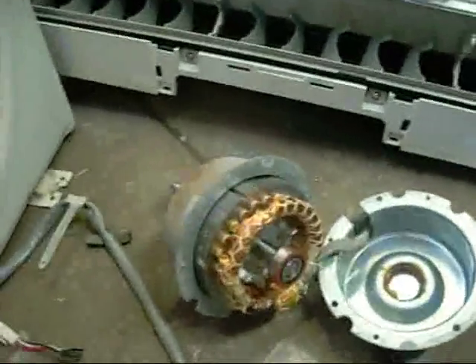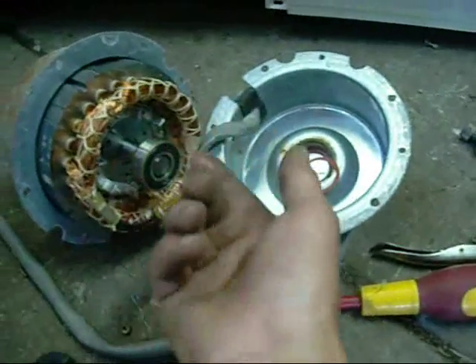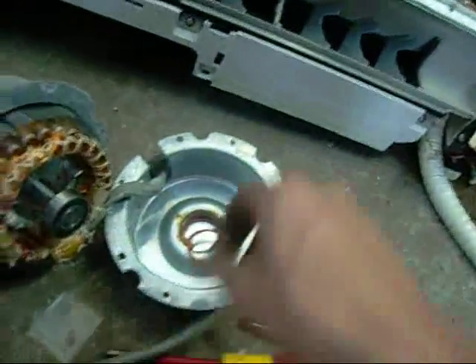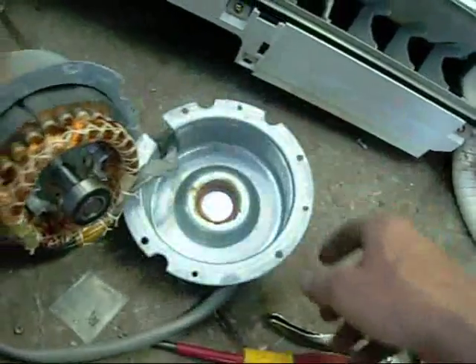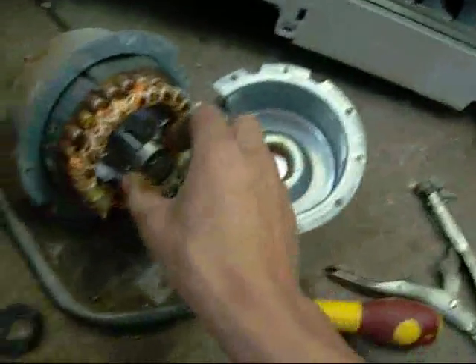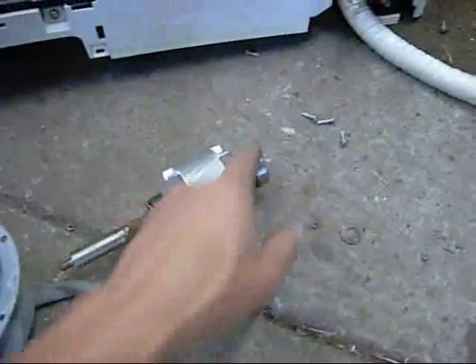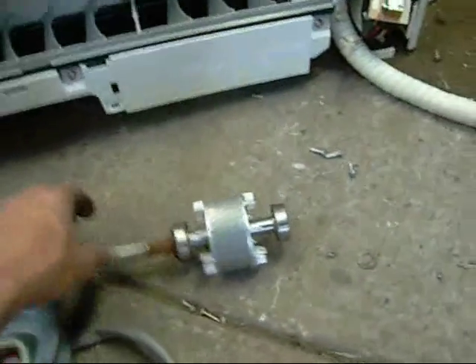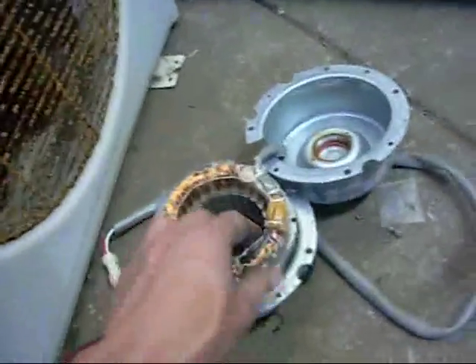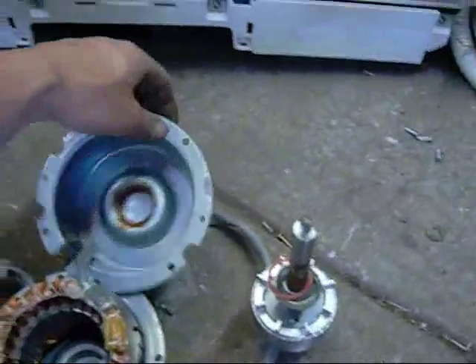This is a fan motor out of a slightly larger Mitsubishi unit. They have rubber sealed bearings - you can pop the seals out with the tip of a sharp knife and pack more grease into them, but they are susceptible to rusting very quickly. The housing isn't really sealed and does have drain holes, but water will still ruin the bearings. The motor insulation should be pretty right, but bearings are your main concern along with any contactors, relays, and cleaning and drying any electrical connections. If there's mud and crap in the printed circuits, you could be in a bit of trouble.